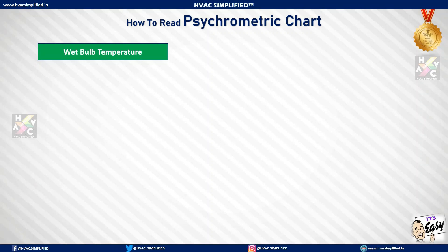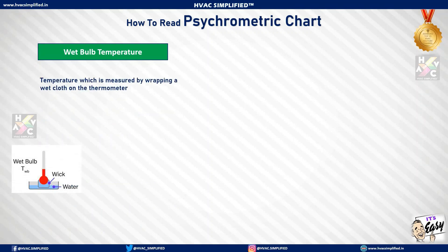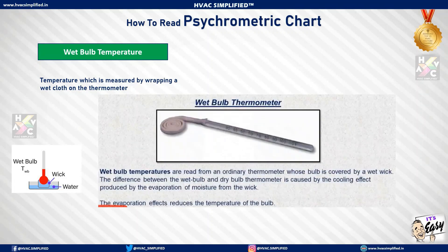Wet bulb temperature is the temperature measured by wrapping a wet cloth on a thermometer. Wet bulb temperature is read from an ordinary thermometer whose bulb is covered by a wet wick. The difference between the wet bulb and the dry bulb temperature is caused by the cooling effect produced by the evaporation of moisture from the wet wick.